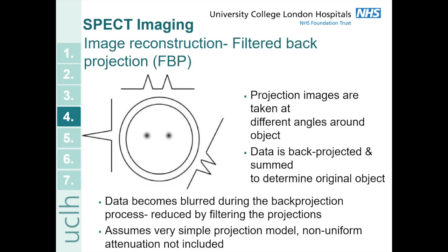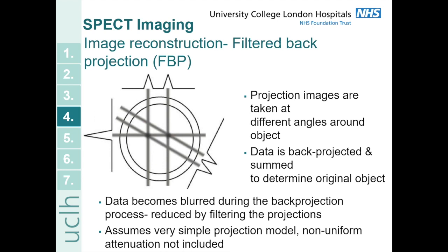Filter back projection is the simplest form of image reconstruction. Projection images are taken at different angles around your object, and the data is then back projected into the image space and summed to work out what the original object looked like. In the diagram there are two sources in the middle imaged at three different angles. For back projection you draw a straight line from your detector through imaging space for each projection, and these overlap where the sources actually are. With enough different angles the overlap shows you where the counts are. The data becomes blurred because you don't know where along the line the source is, but you can reduce this blurring by filtering the projections. This technique assumes a simple projection model and cannot account for non-uniform attenuation within the imaging space.